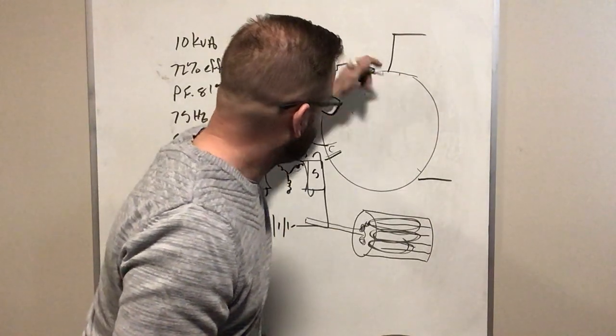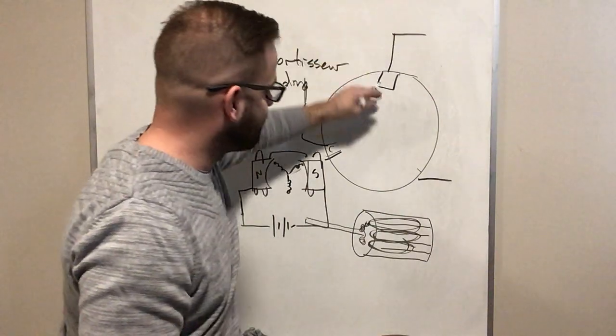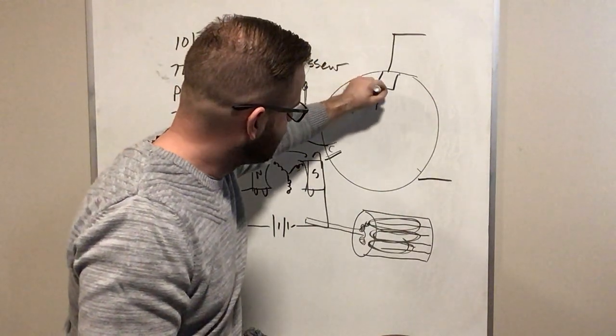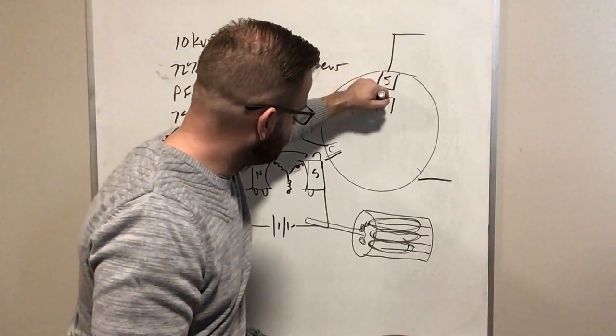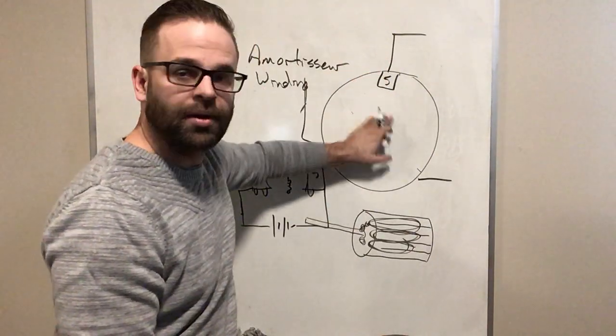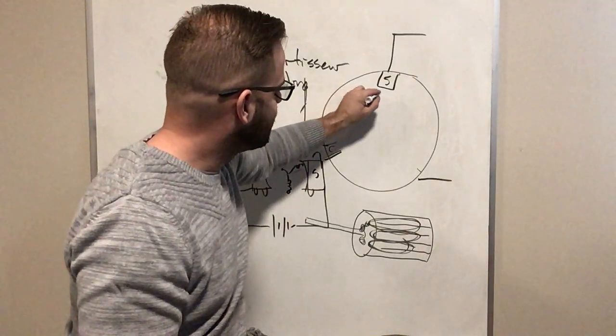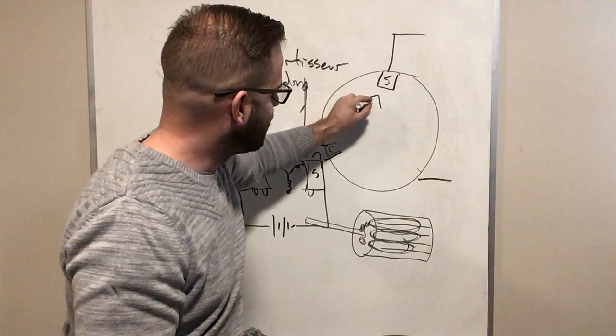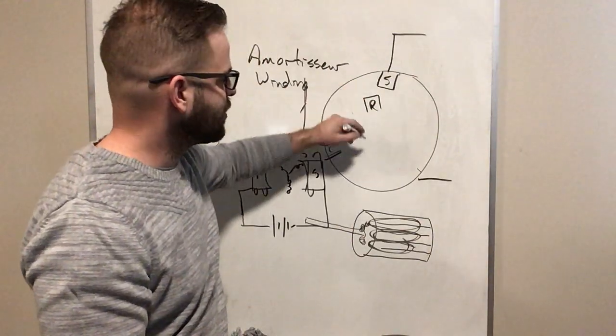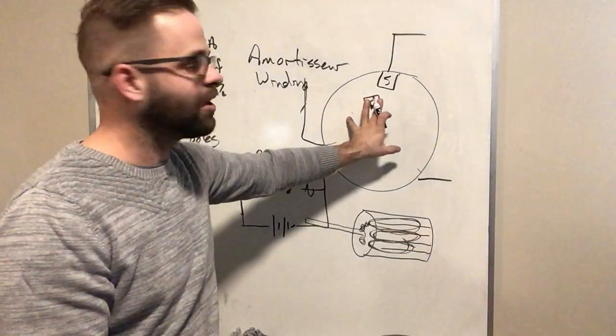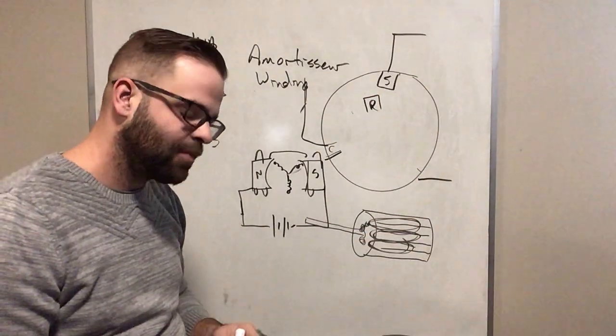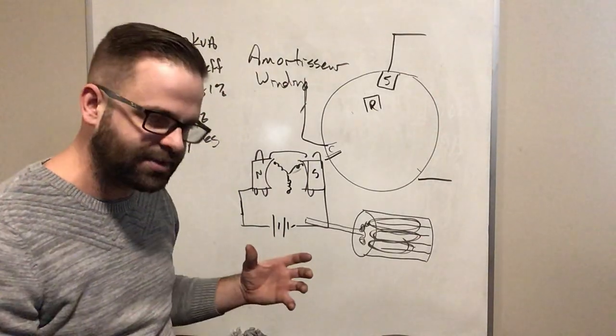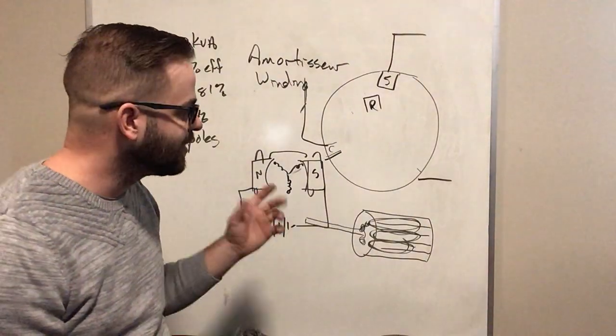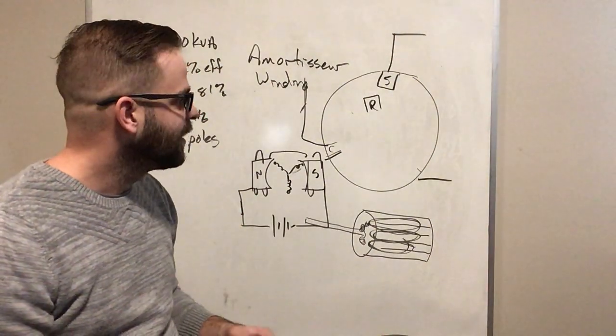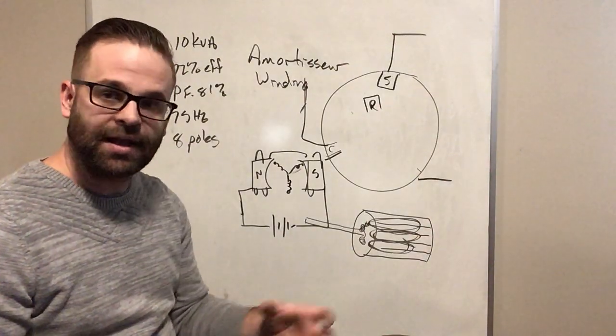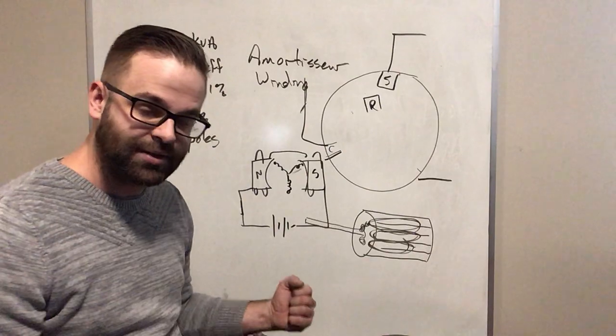And I know these actually are stationary and the magnetic field is spinning, but if that's the pole of the motor and this is unloaded, so this would be stator, rotor, and they're lined up. As I go to load down that motor, what ends up happening is it ends up getting stretched behind slightly. So now my rotor is slightly behind, but it's still moving at the exact same speed. And it will remain at that speed until it gets pulled out of step. And the problem is when you finally get to that point where you've overloaded that motor, it'll pull it out of synchronism. And just like that elastic band, once you put too much weight, that elastic band's going to break.